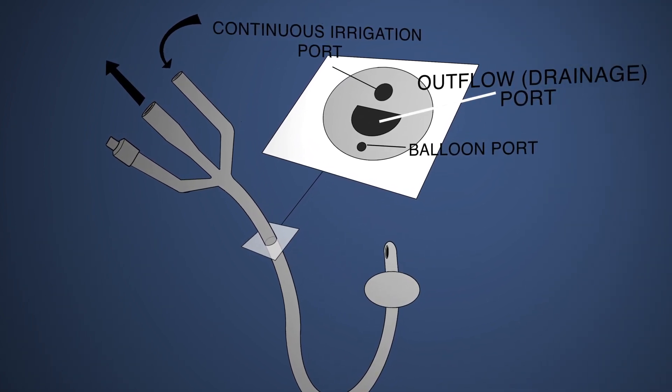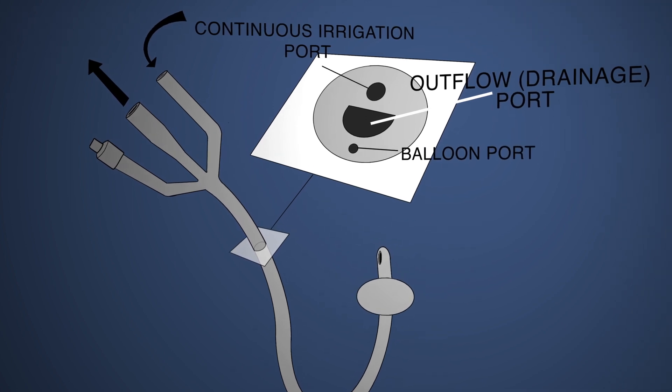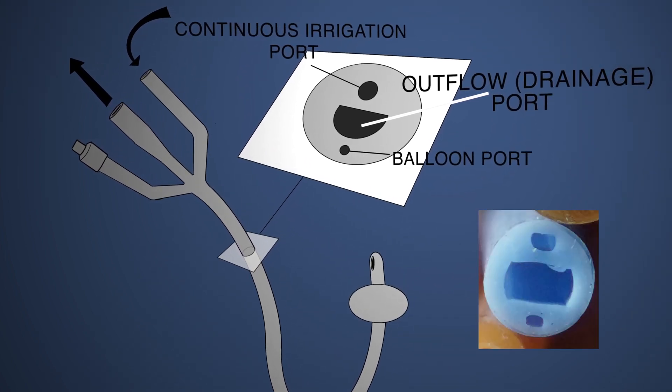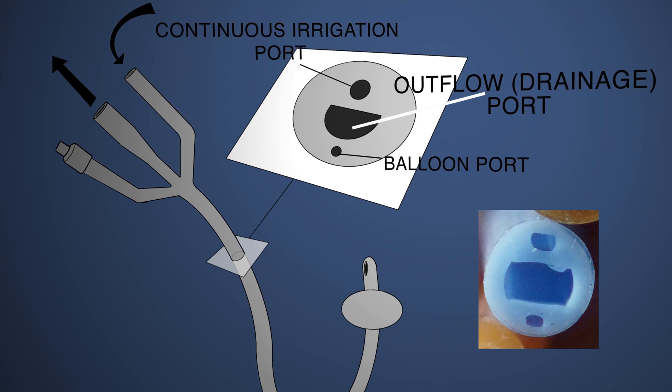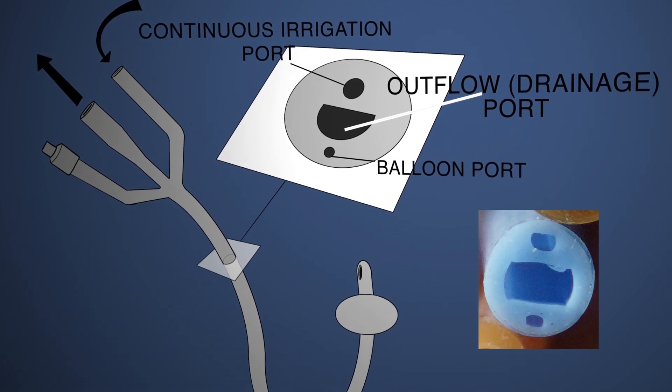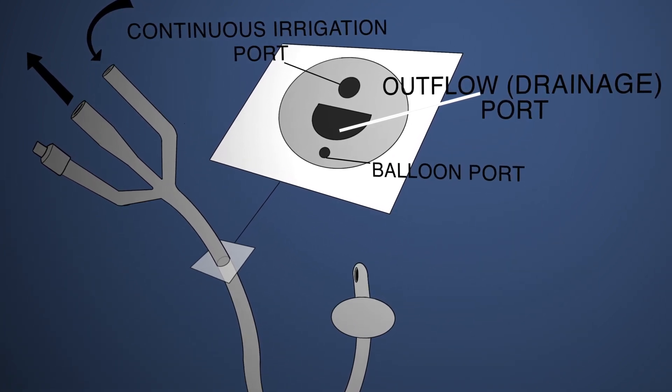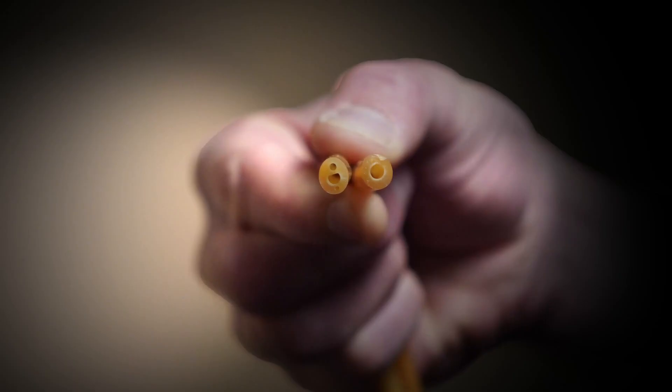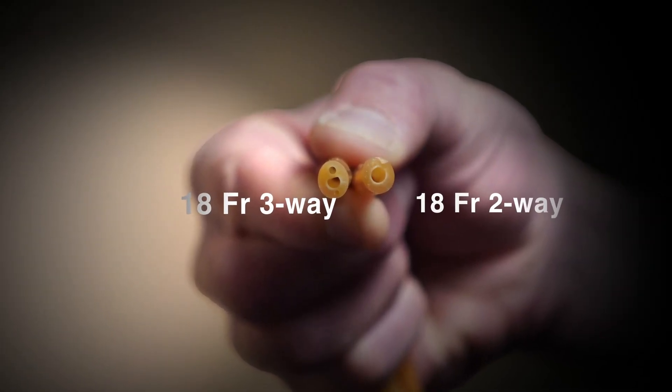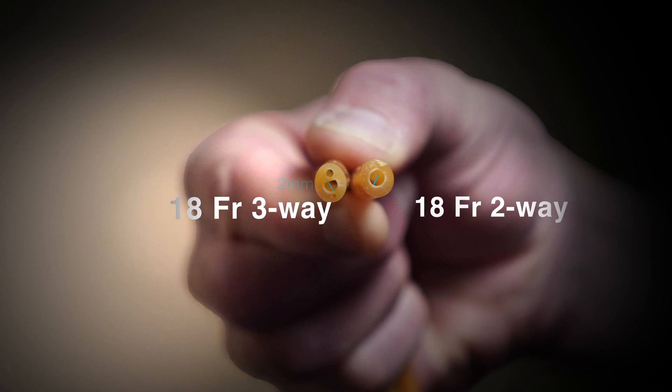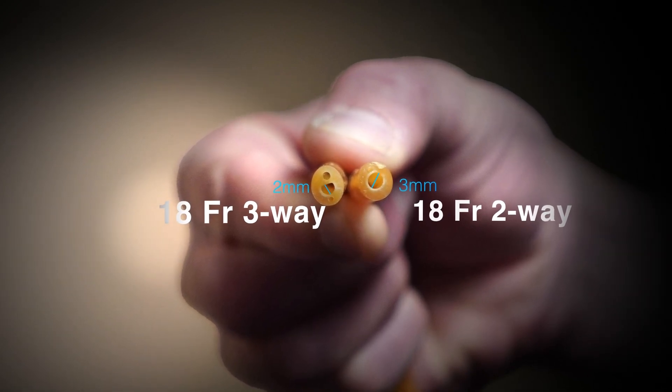This additional irrigation port is designed to add fluid to the bladder with continuous irrigation when there is active bleeding present. The catheter itself and the irrigation does not actively stop the bleeding. Rather, the irrigation dilutes the bleeding when present so that clots do not form. This additional port decreases the channel size of the catheter because this is an additional channel going through the same tube.